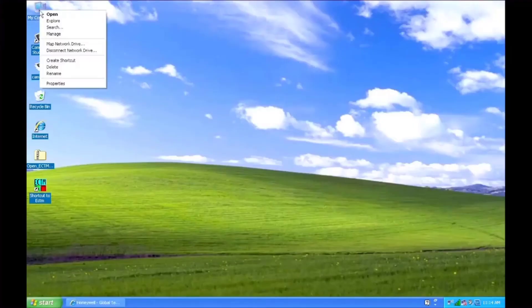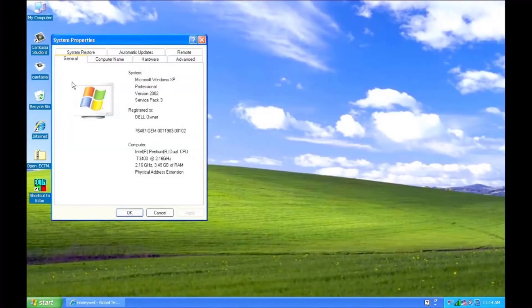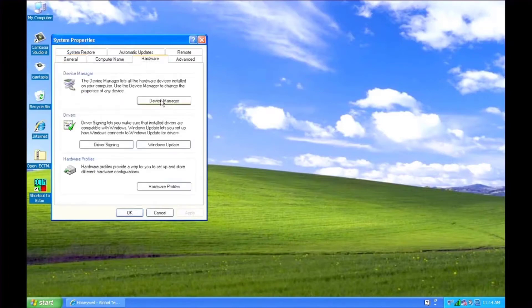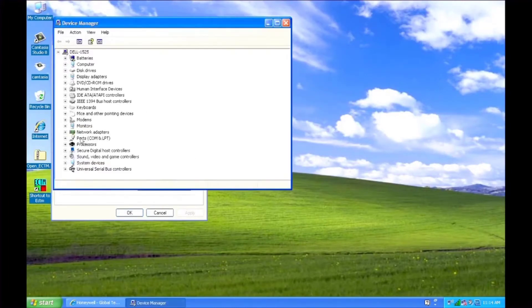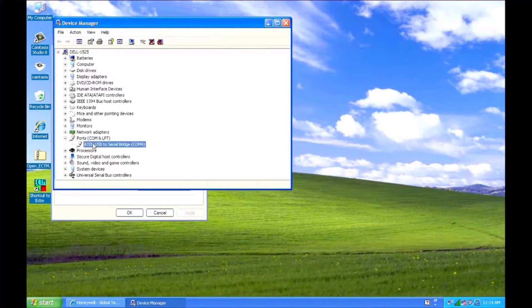Next, you'll need to configure the ECTM software to use the proper COM port. Connect the laptop to the DEEC and make sure the DEEC is powered on and in auto mode. Go to the device manager. Find USB to serial bridge and make a note of the COM port.